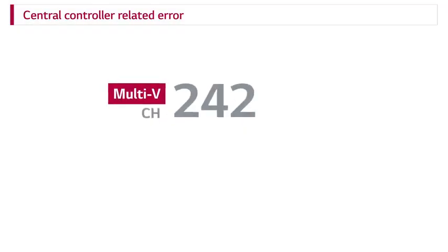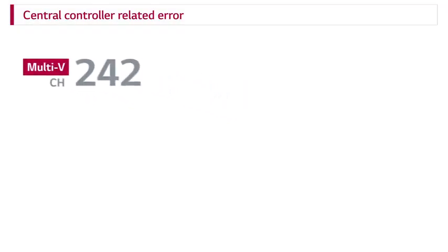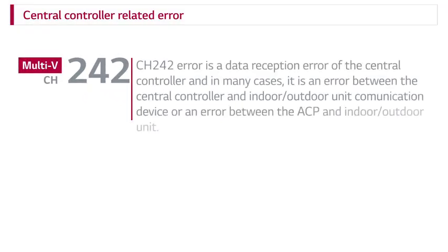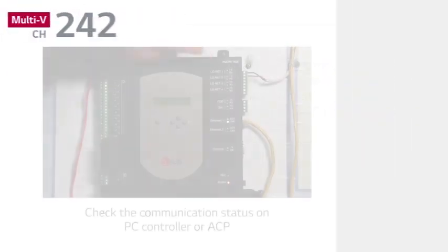Central controller related error: CH242 is a data reception error of the central controller. In many cases, it is an error between the central controller and indoor-outdoor unit communication device, or an error between the ACP and indoor-outdoor unit.